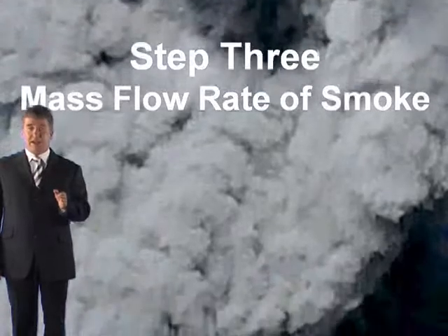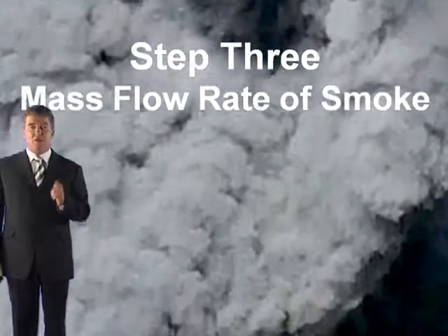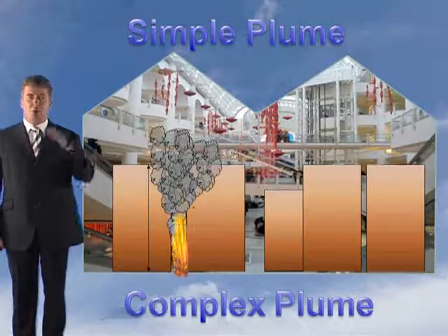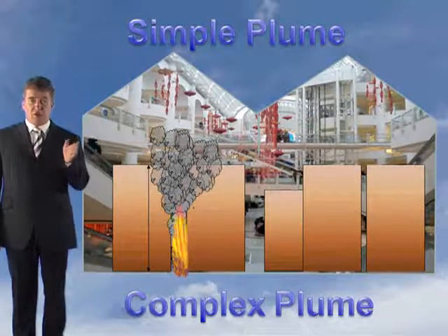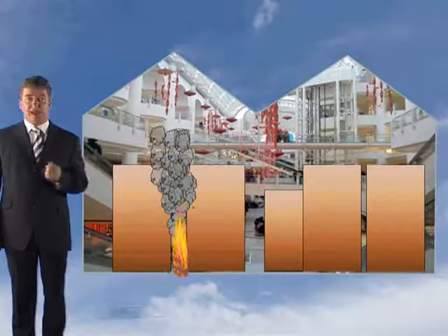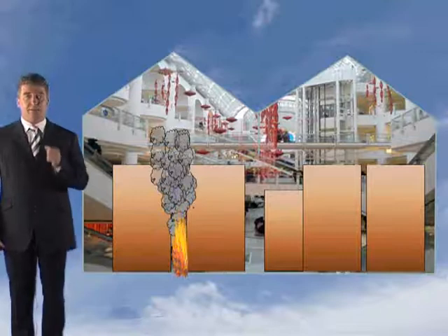Step three is determining the mass flow rate of smoke — how much smoke is that size fire going to give off in our reservoir, in our compartment? We firstly need to establish whether this is a simple plume or a complex plume. In this case, the design fire is located in the reservoir where it's going to be extracted, and so it's classified as a simple plume.